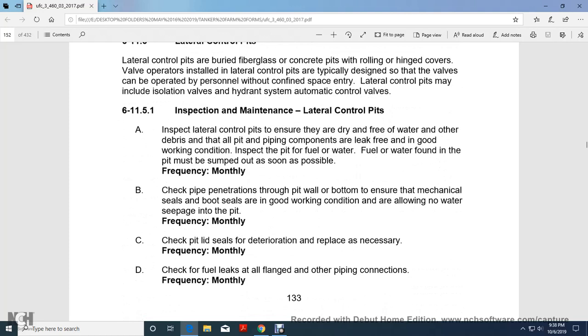Lateral control pits. Lateral control pits are buried fiberglass or concrete pits with a hinged cover over the valve. The operators install lateral control pits, typically designed so that the valves can be operated by personnel without confined space entry. Lateral control pits may be installed with the isolation valve of the hydrant system automatic control valves. Inspection and maintenance for the lateral control pits.